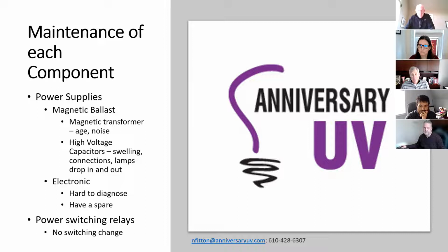So you want to pay attention to the age, and you want to pay very close attention. If you start hearing noise, you're days away from failure on a magnetic ballast. And you don't want that ballast to go down, because if it goes down, these are not stock items, and it's going to take weeks to get a new magnetic ballast.